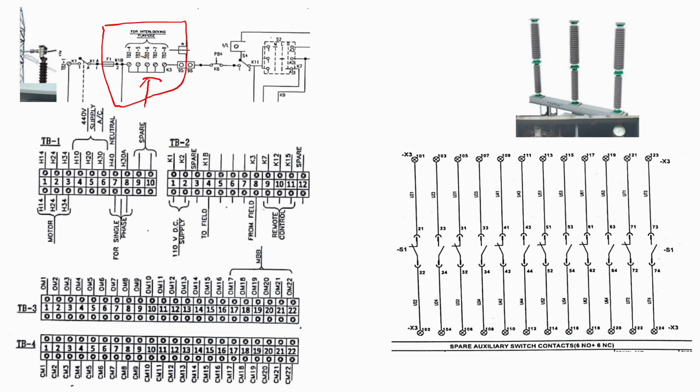So for that you need an auxiliary contact of the circuit breaker, because the isolator wants the breaker condition, and we know how we can get the breaker condition. So for that we need to use the auxiliary contact of the circuit breaker. You need to use the close contact of the circuit breaker. NC contact means, my point is you have to use the NC contact. How? So this is K1B and this is K3, okay? This is the closing circuit of the isolator.